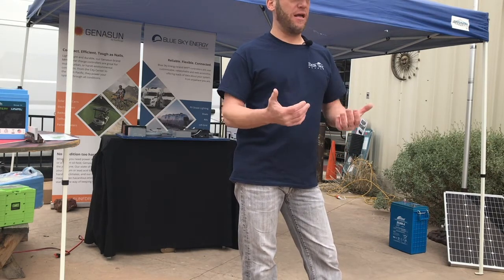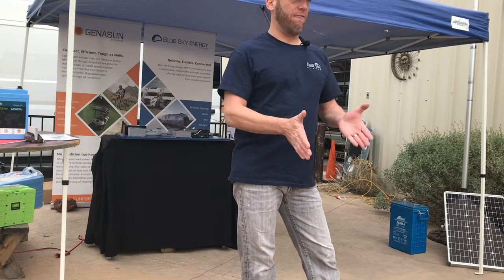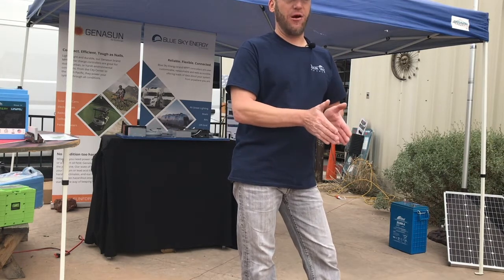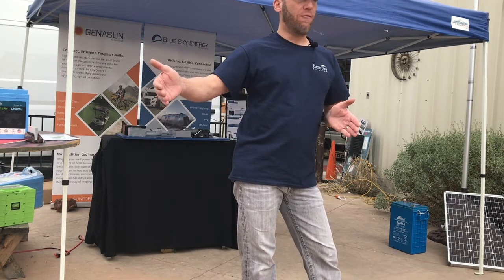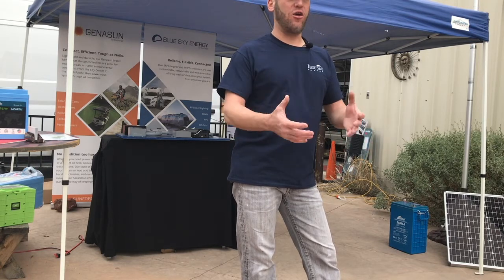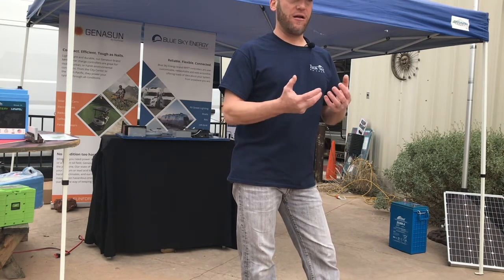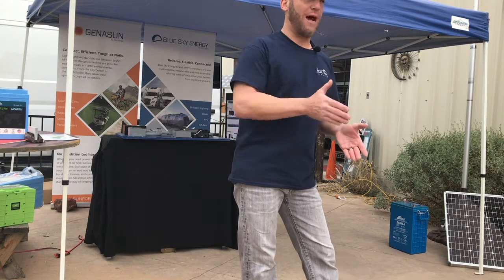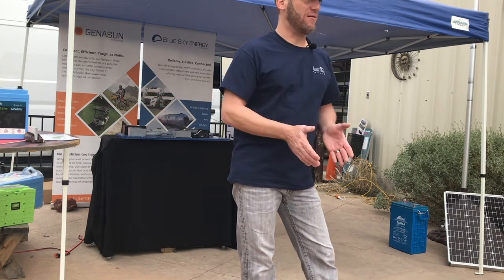If somebody does want to equalize an AGM, I'd recommend a very short equalization period over multiple days in a row versus one long period where heat can accumulate inside your battery and all of a sudden you lose it. So if you want 6 hours, I want 1 hour a day for 6 days, not 6 hours in a row.